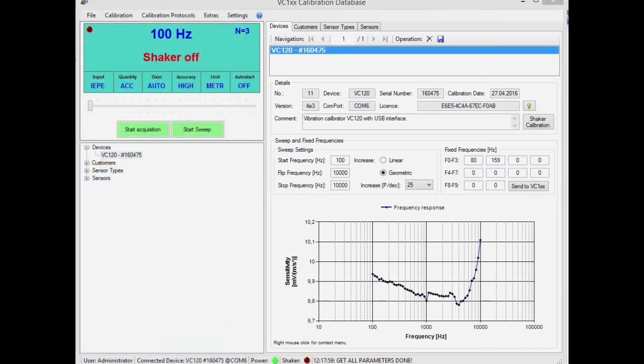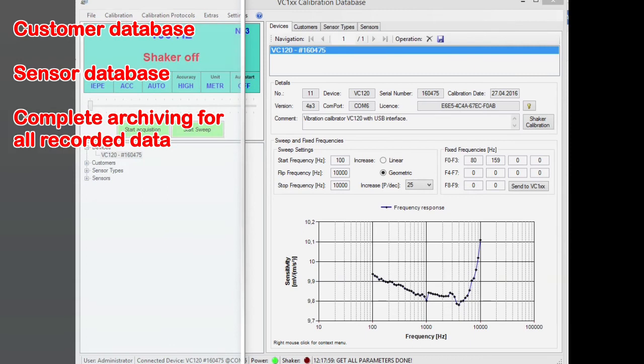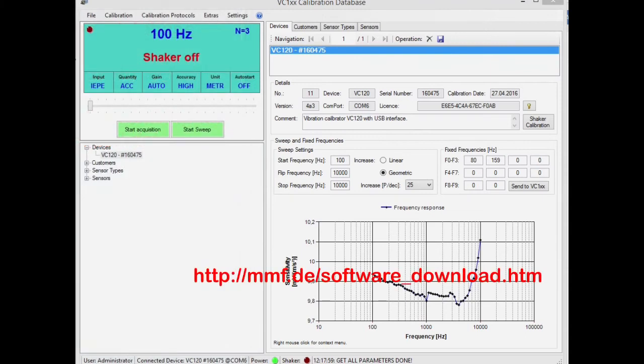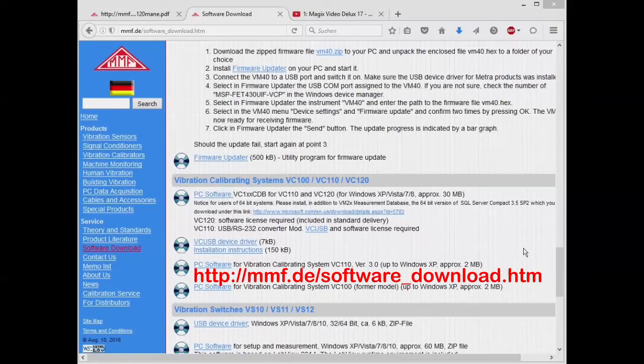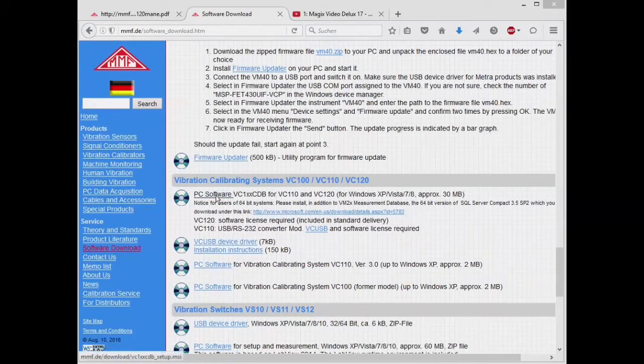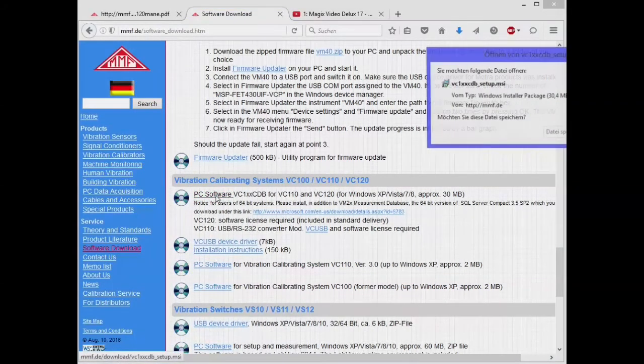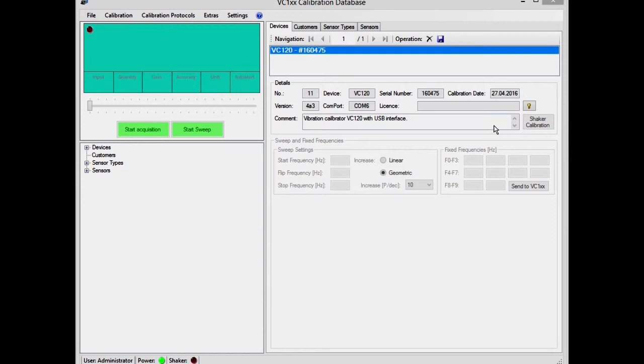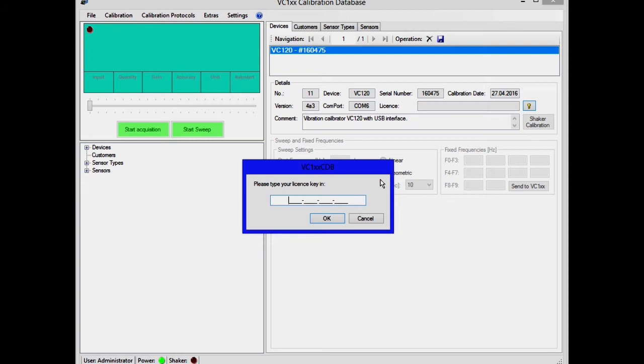The software offers the basic functions of modern calibration technology, including a customer database, sensor database, and complete archiving for all recorded data. The VC1XX calibration database software, including the instrument driver, can be downloaded from our website. Connect the VC120 to your computer with the mini USB cable and switch it on. When connecting up for the first time, you'll be asked to install the instrument driver. Now start the calibration database software. The instrument will appear on the display with its serial number.